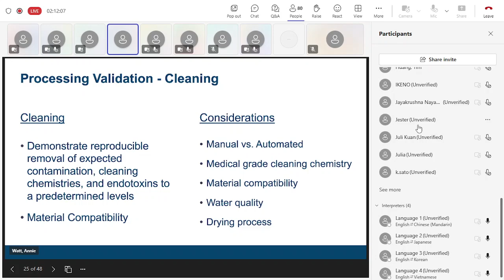The drying process should also be defined. How will the device be dried? Is it air dried? Is it a drying cabinet? Is it part of the washer disinfector cycle? We have to have considerations for all of these: the temperature, the device design, the material of construction, and the total time required to dry the device. And that's just for cleaning.